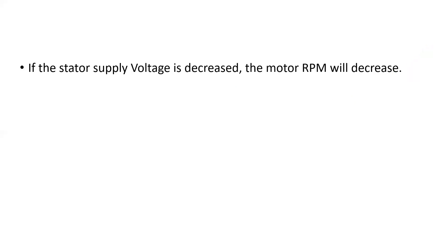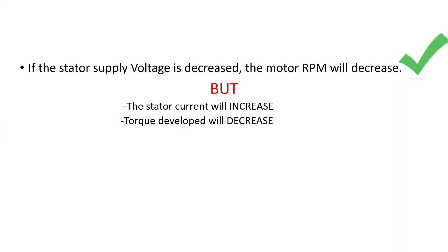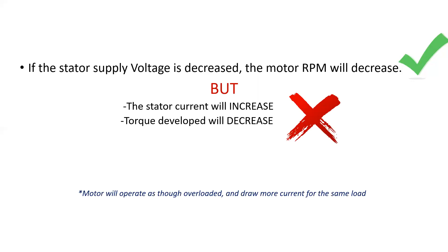If the stator supply voltage is decreased, the motor RPM will decrease as well. However, exactly the same problems occur — the stator current will go up and the torque developed will decrease. In effect, the motor will operate as though it's overloaded and draw more current for the same load.